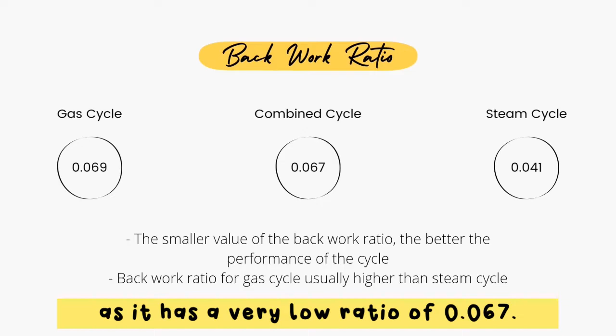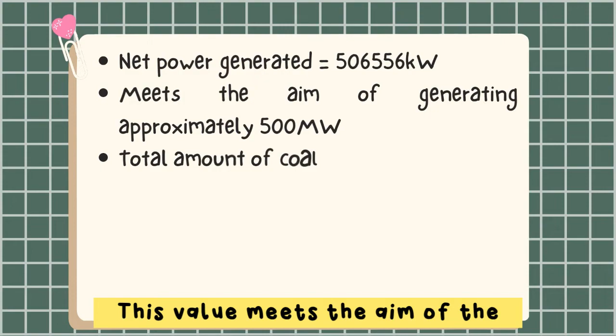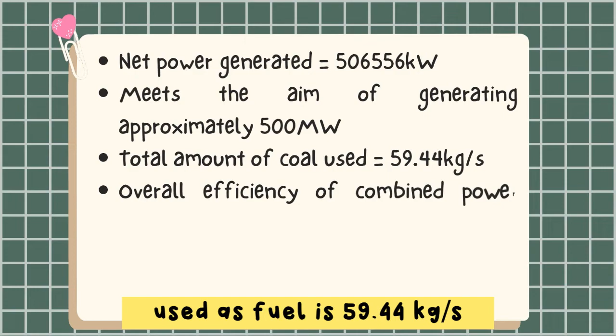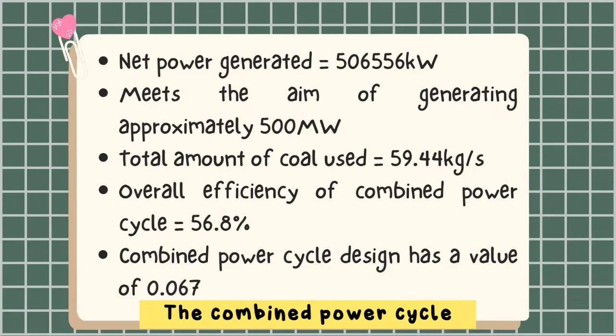For conclusions and recommendations: the net power generation is 506,556 kilowatts, approximately equal to 500 megawatts, meeting the aim of designing the combined gas steam power plant cycle. The total amount of coal used as fuel is 59.44 kg per second in the combustion chamber to produce hot flue gas to turn the turbine. The overall efficiency of the combined power cycle is 56.8%, which is good, and the back-work ratio is 0.067.